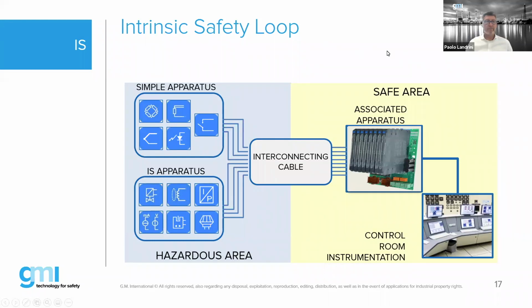Okay, exactly. The intrinsic safety loop is that - just a slide that resumes what we said till now. So you have a simple apparatus, or IS apparatus, devices that are installed in the hazardous area. It can be zone 0, zone 1, or zone 2 also. And you have a safe area where there is a control room. In this case, a connection between the control room, where there is a DCS or PLCs, is not permitted because of energy. So we say that we have to control the initial energies that go from the safe area to the hazardous area.